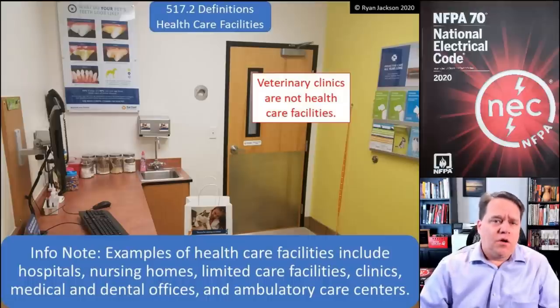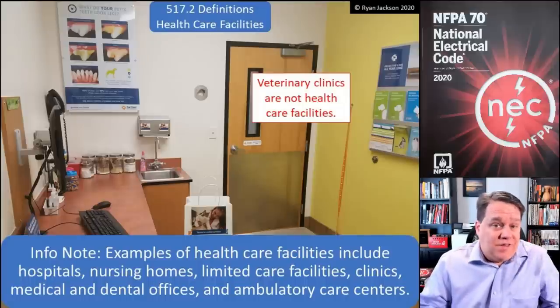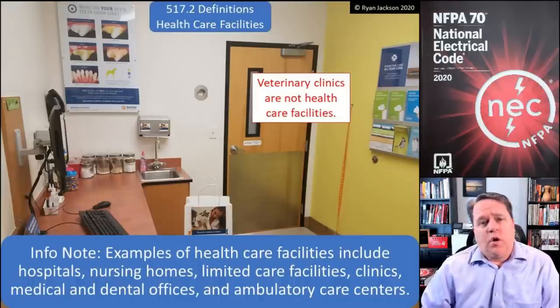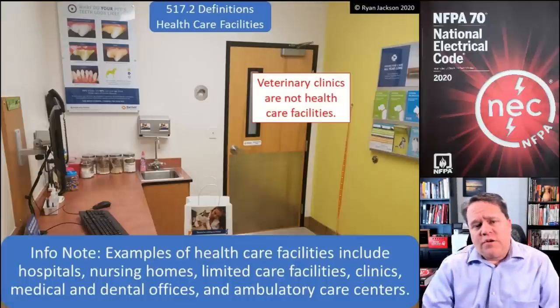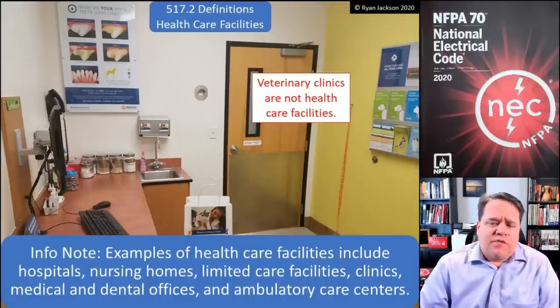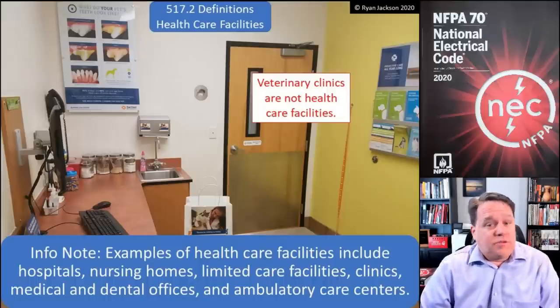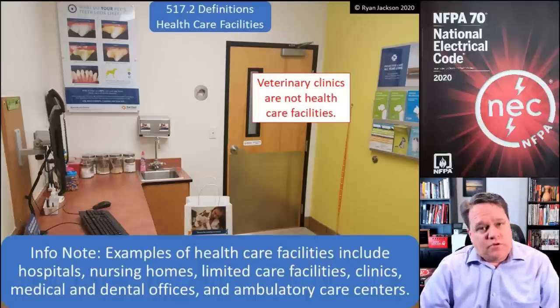If you're wiring a veterinary clinic, you would not be reading article 517. The NEC covers veterinary clinics, but it doesn't have any special rules for them — you'd wire a vet clinic no differently than an office building. An informational note tells us that examples of health care facilities include hospitals, nursing homes and limited care facilities, clinics, medical or dental offices, and ambulatory care centers.